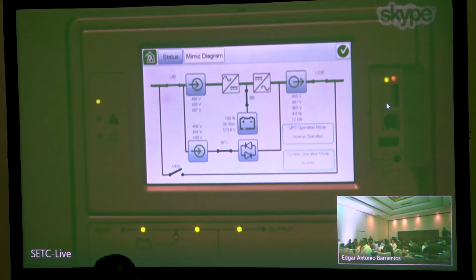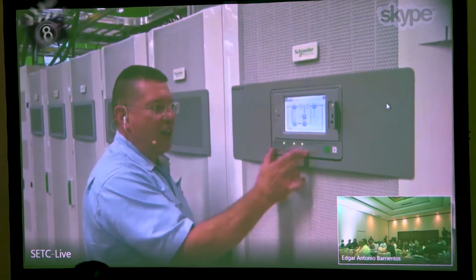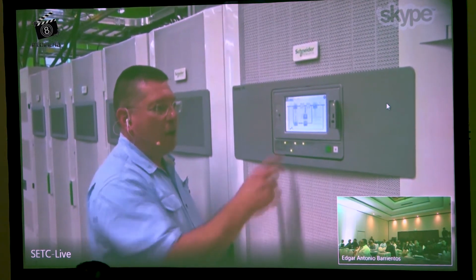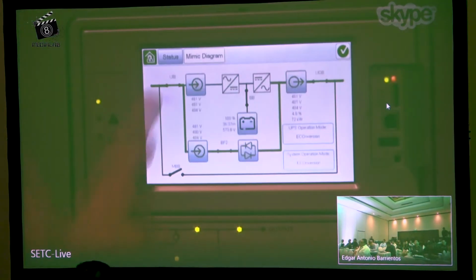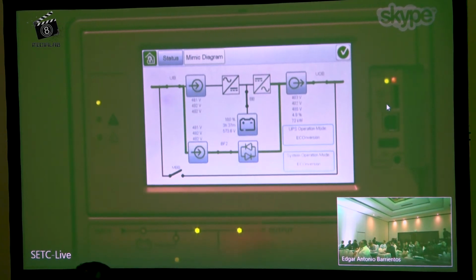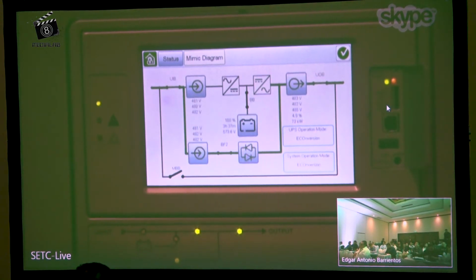It takes about 30 seconds to get there, because we're checking about 150 points in each cabinet. That information has to be transmitted to the IOC, the input-output main controller, and everything has to be stable before we change. We'll hear contactors open and close, see the screen change, and see the LEDs change. And there we go - LED change, screen change. You heard the contactors. Now we're in E-conversion mode, okay.